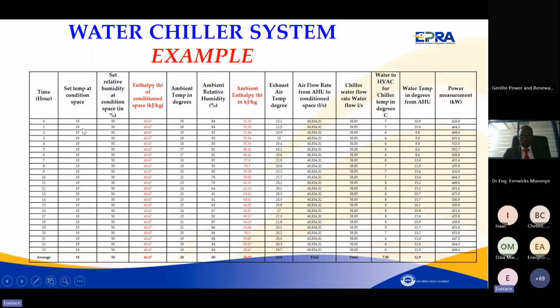This one tells you the control system was very good. It is set at 19 degrees. The reason for checking the set point condition is to see whether it has deviated. Probably it requires 19, and sometimes you find it is 18 or 17. That means it's a red flag because you'll be overworking your cooling system. Then you set the humidity at 50. That one was okay. Then the enthalpy of the conditioned space.